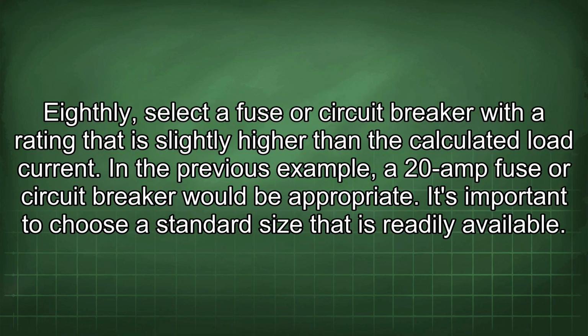Eighthly, select a fuse or circuit breaker with a rating that is slightly higher than the calculated load current. In the previous example, a 20 amp fuse or circuit breaker would be appropriate. It's important to choose a standard size that is readily available.